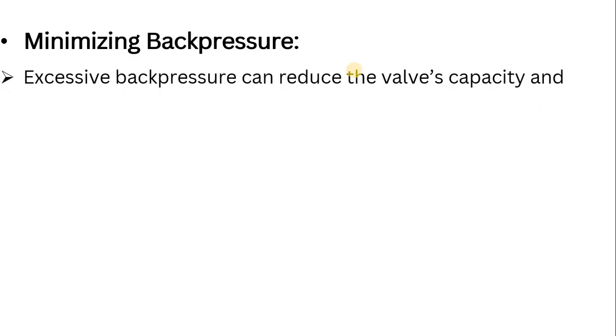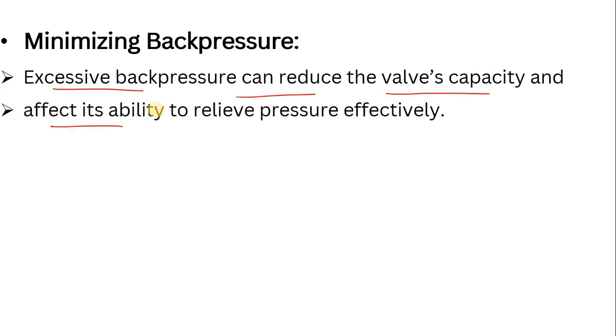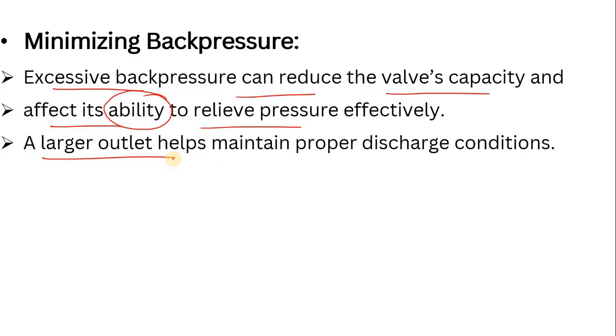The third reason is minimizing back pressure. If excessive back pressure builds up at the outlet of the PSV, it can reduce the valve's capacity to operate. If the PSV is sized improperly, excessive back pressure can significantly affect its opening, and if the system is over-pressurized, the PSV will not pop up. That's why a larger outlet helps maintain proper discharge conditions. In upcoming videos, I will show how back pressure affects the calculation.